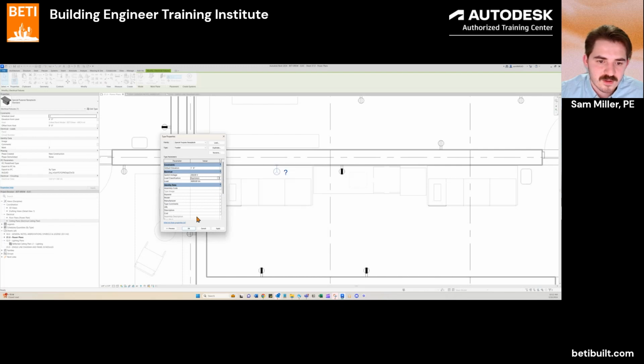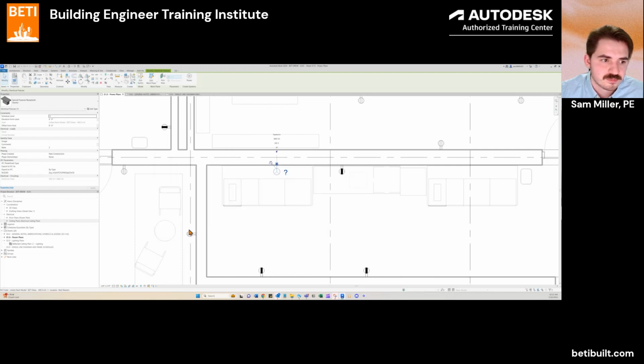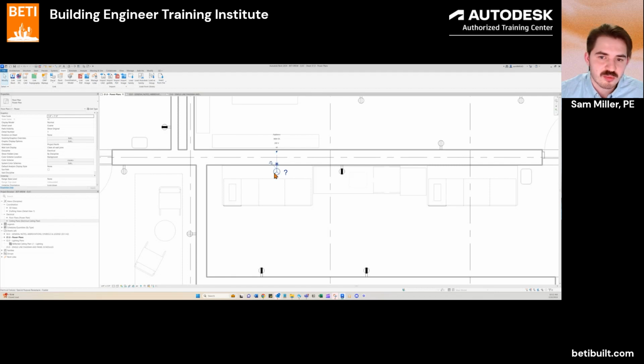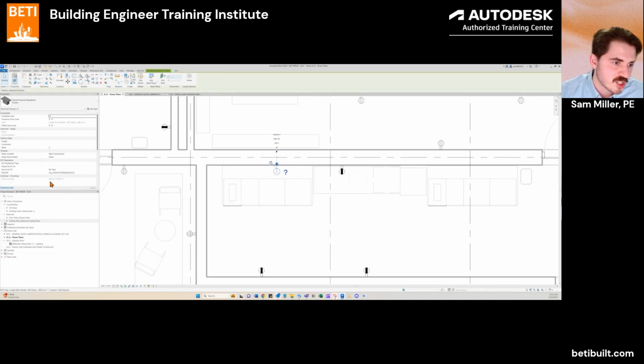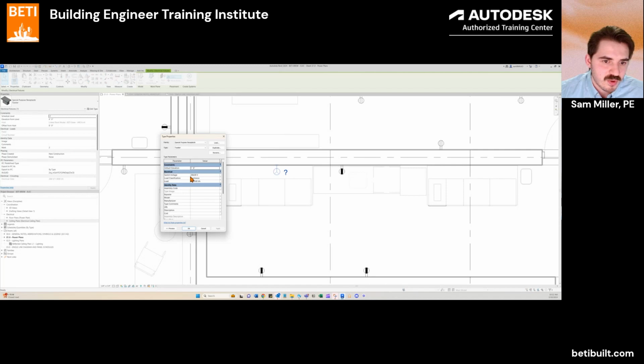So I'll use appliance here, hit apply. Now you can see my 208 volt, 1 pole, 3600 VA. This is actually still a problem, because if you remember from last week's homework, 208 volt requires 2 hot wires, so it's always going to need 2 poles. Since this is grayed out, we don't see number of poles or any way to change it here, or phase, in this type editor.